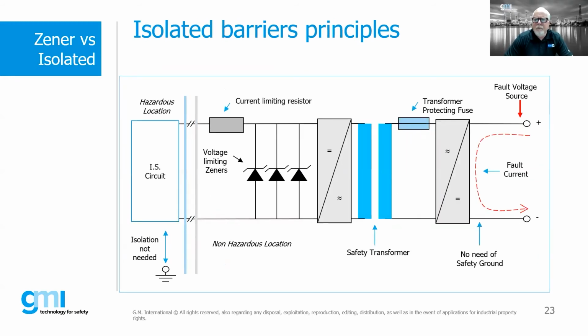Now, an isolated barrier has a couple extra components inside. We still have a fuse, resistors, and Zener diodes, but now we've incorporated a safety transformer. In this instance, if we have a fault condition coming in, it hits this transformer and stays on this side of our safety transformer, so that fault condition isn't passed through.